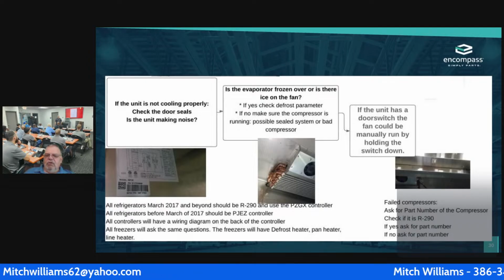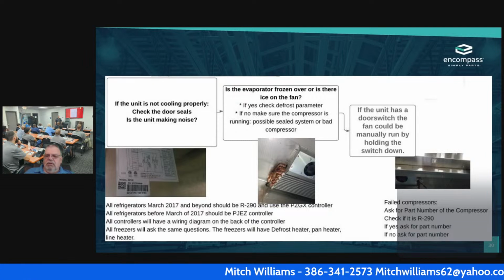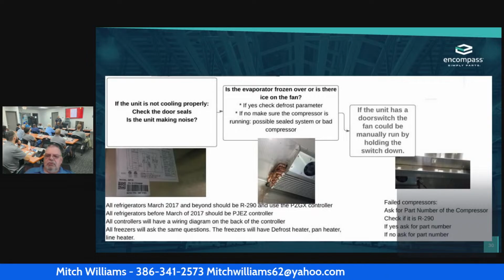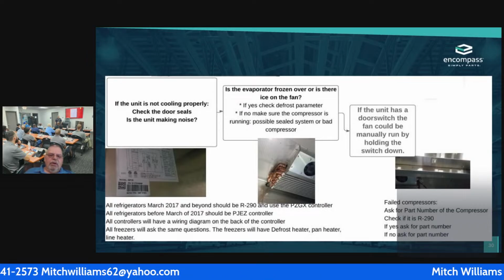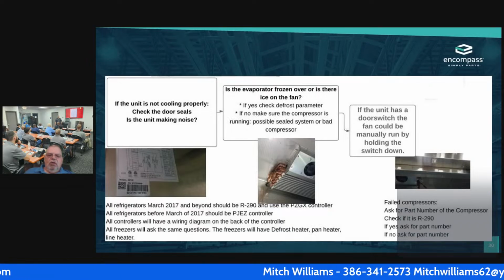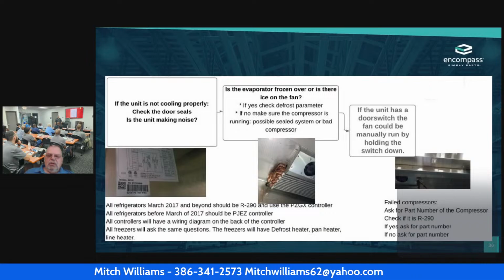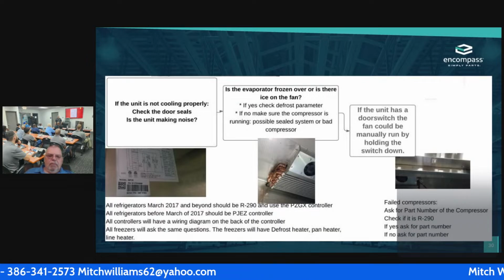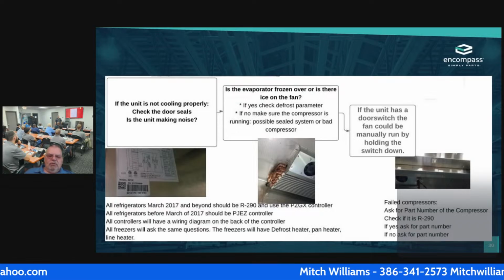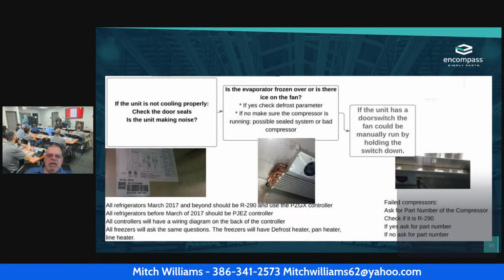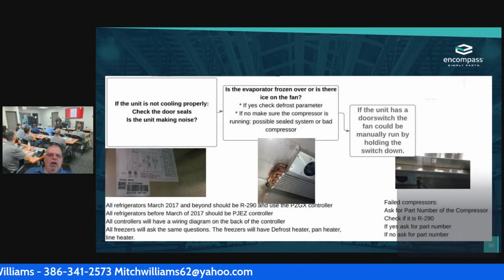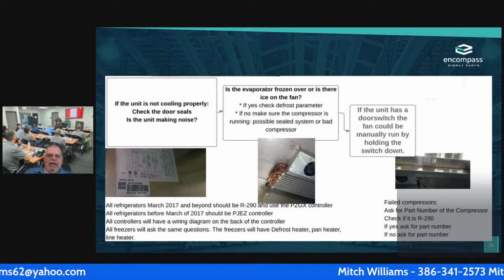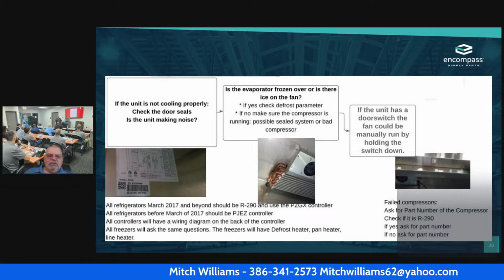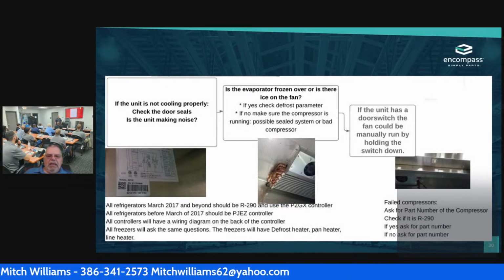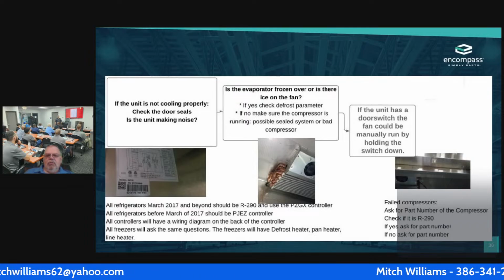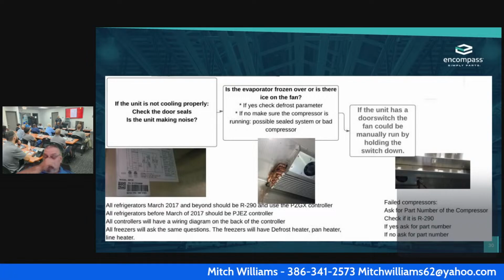Okay, failed compressors. I'm going to ask if it's an R290. Ask for the part number. If not, ask for the part number. So all refrigerators March 17th and beyond should be R290 and use the PZGX controller. All refrigerators before March of 2017 should be the PJEZ controller. Okay. All the controllers have a wiring diagram on the back of the controller. All the freezers will ask the same question. The freezer will have a defrost heater and a pan heater line. These are so that the water has time to travel down to the drain.